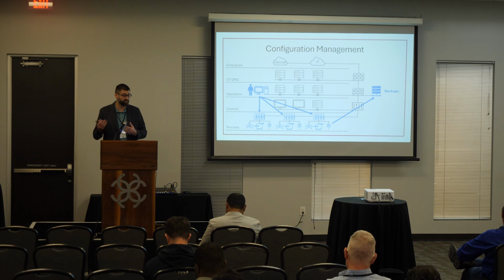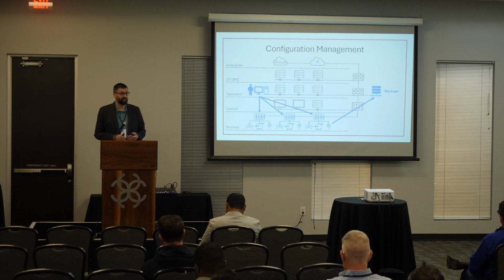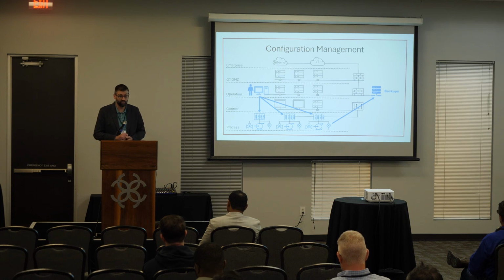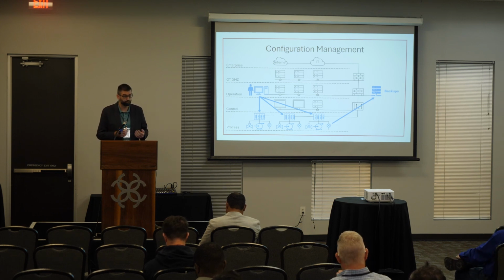If I have to replace equipment, anybody deal with a lightning strike ever? Can you control lightning? Has anybody seen it go right past the lightning protection and still blow up everything in that panel? Lightning does what lightning wants to do. Despite the best efforts, the best lightning protection out there, I've seen it blow up entire panels. How quick can I get that PLC back online? Pretty quick if I've got a backup of it. If I've got a configuration file that I can just load on, slap a new PLC in that panel, hey, we're back up and running in no time.